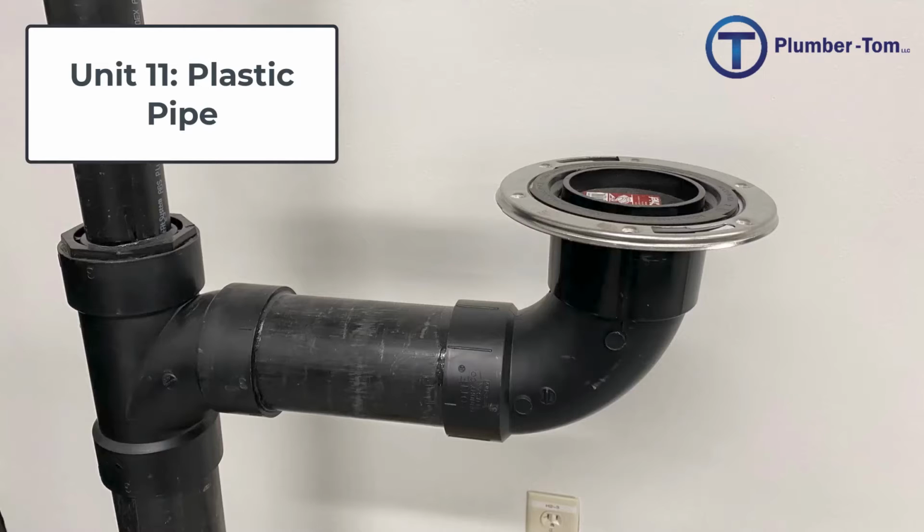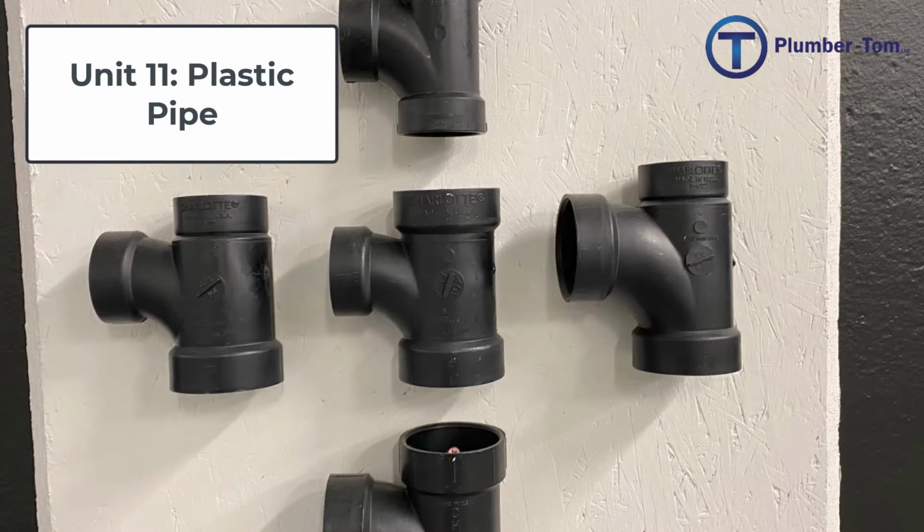Interesting other note about ABS. It was used for quite a while, as mentioned, but ABS has a higher tensile strength than other types of plastics. That means it is pretty strong, but that makes it stronger and harder. Because of the rigidness of ABS, it is more prone to cracks. That decreases its lifespan, and that's also why we're not using it as much as we are PVC, because over the last decades we've seen that ABS will crack, and there are many drainage leaks in people's homes because of cracked ABS pipe. Fun fact.